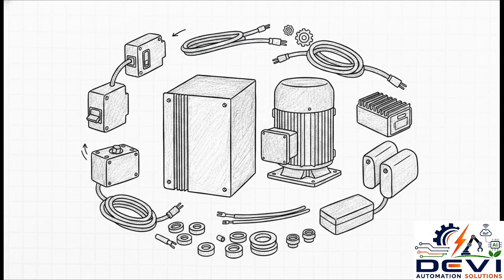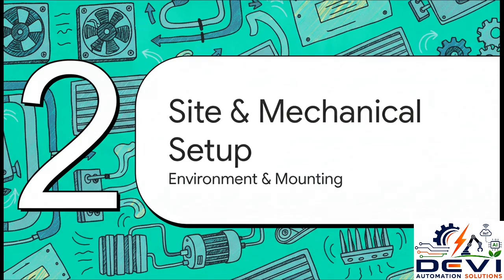Look, everyone remembers the VFD and the AC motor, right? But true professionals know you need the whole package. You need your protection devices like your MCCBs, MCBs, and contactors. You also need your power conditioning hardware, so input and output reactors and EMI filters to handle those pesky harmonics. Depending on your application, you might even need a brake resistor. And crucially, having the right power, control, and earthing cables alongside proper cable glands and lugs is a game changer. It totally prevents that uniquely frustrating moment of having to halt an entire installation just because you're missing a 50-cent ferrule.